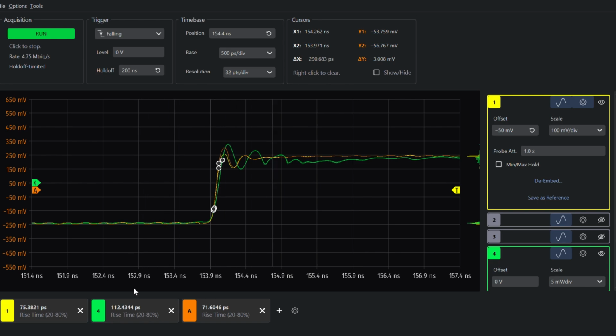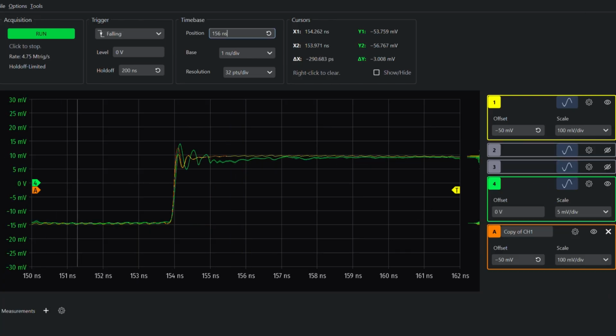Now, looking at the probe response, its rise time is around 110 picoseconds, which is the fastest it's ever going to be given its bandwidth. And in this context, we're not really expecting an accurate representation of the source because the rise time of the source is too fast for the probe, which will lead to distortion. And also the measurement point of the scope and the probe are separated by around 1 meter of coax.